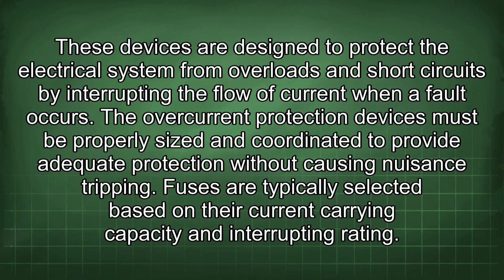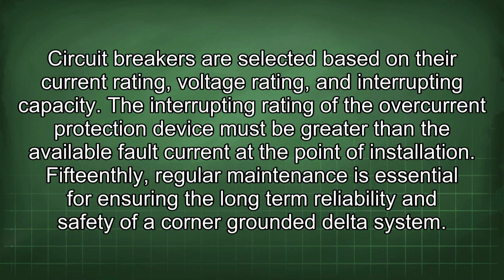Fuses are typically selected based on their current carrying capacity and interrupting rating. Circuit breakers are selected based on their current rating, voltage rating, and interrupting capacity. The interrupting rating of the overcurrent protection device must be greater than the available fault current at the point of installation. 15thly, regular maintenance is essential for ensuring the long-term reliability and safety of a corner-grounded delta system.